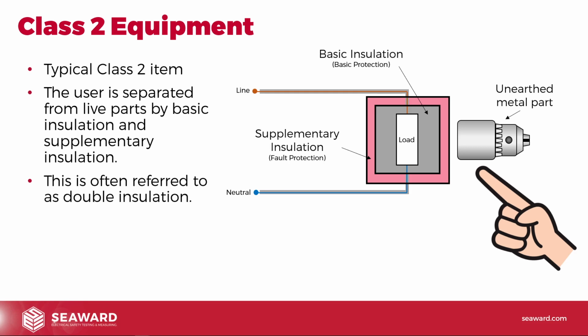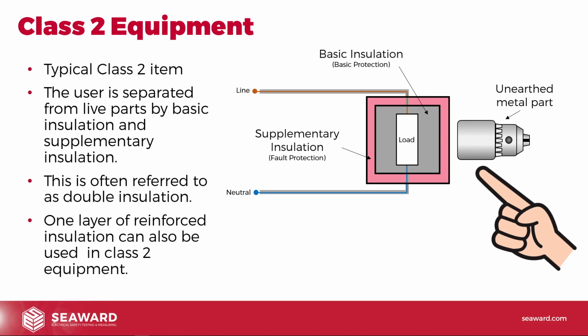So don't automatically assume that class 1 equipment is shiny metal and class 2 equipment must be a big blob of plastic. It isn't necessarily that clear. The difference is how are we protected from the live parts? How has the designer done that? And sometimes, again, it can be quite difficult to actually identify what's been done. So one layer of reinforced insulation can also be used in class 2 equipment. So we think of double insulated equipment as having 2 layers of insulation. One that provides the basic protection and another one that provides the supplementary insulation.